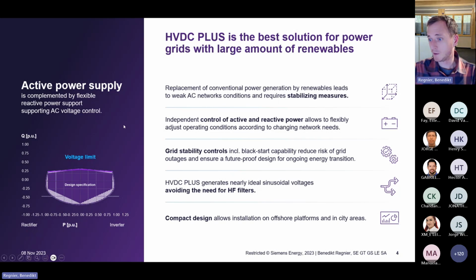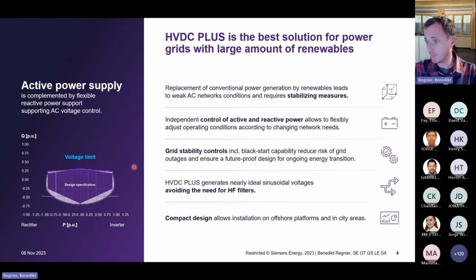What we can see here, what is one of the big features, let me also switch to my pointer. Yeah, we can really use the active power and the reactive power. It's not only that we use active power and reactive power is coming as some kind of side effect and we cannot control it. Here, we really can control both independently, and this gives us a lot of opportunities for stabilizing the grid further, and not only for power transfer.